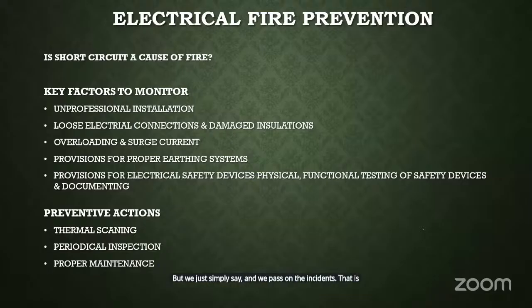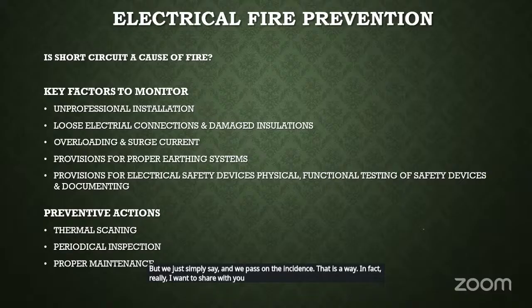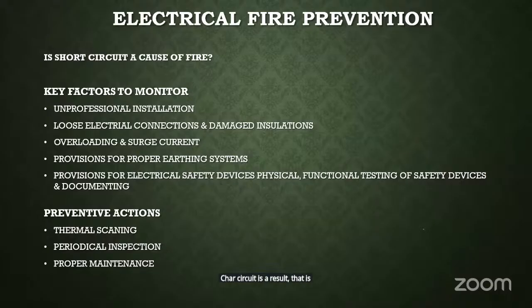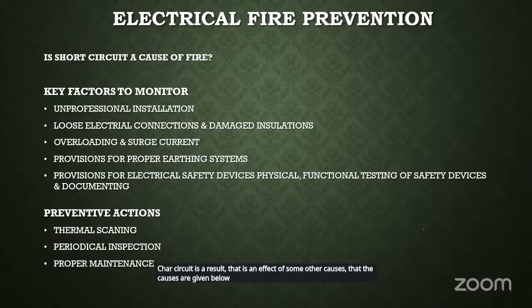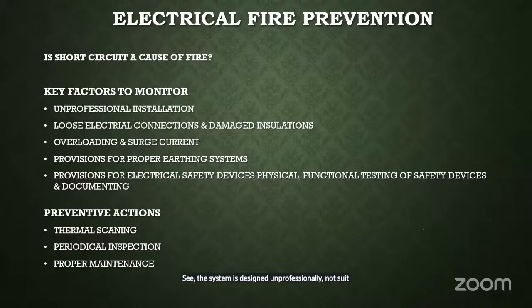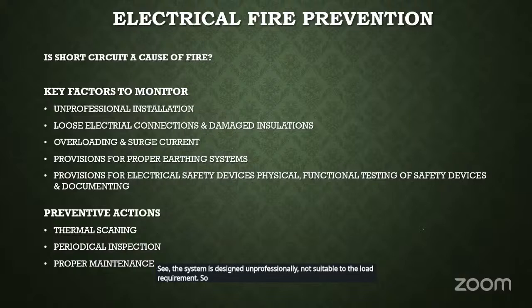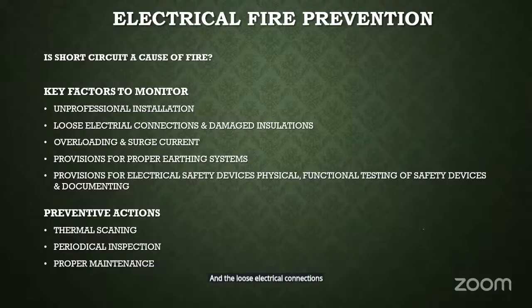That is the way. In fact, I want to share with you, short circuit is not a cause at all. Short circuit is a result. It is the effect of some other causes. The causes are given below. Unprofessional installation: the system is designed unprofessionally, not suitable to the load requirement. So undersized cable or oversized cable and improper or substandard rated quality of substances or equipment. So that is unprofessional installation, and loose electrical connections, damaged insulation, and overloading and surge current.